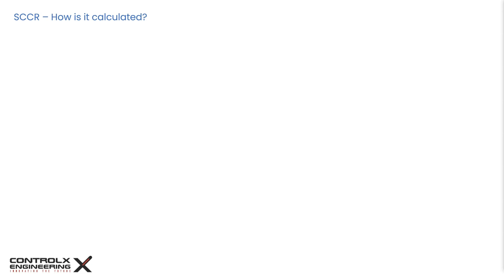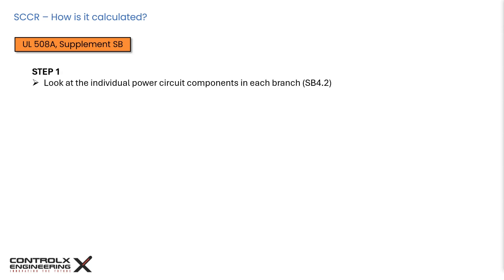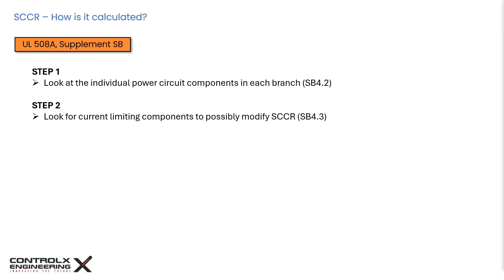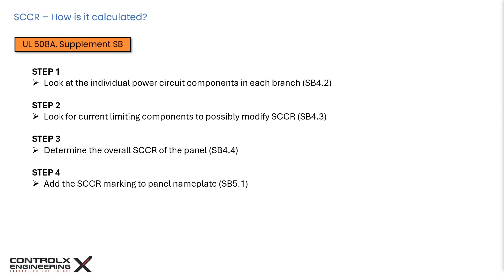SCCR is determined by analyzing the ratings of all components in an assembly, such as an industrial control panel. Each device — like breakers, contactors, and overloads — will have its own individual SCCR, and the overall panel SCCR is based on the weakest link: the component with the lowest rating. According to UL 508A Supplement SB, there are four basic steps: Step 1 — identify individual power circuit component SCCRs per SB 4.2; Step 2 — identify current limiting components per SB 4.3; Step 3 — determine the overall panel SCCR per SB 4.4; and Step 4 — add the SCCR marking to the panel nameplate per SB 5.1.